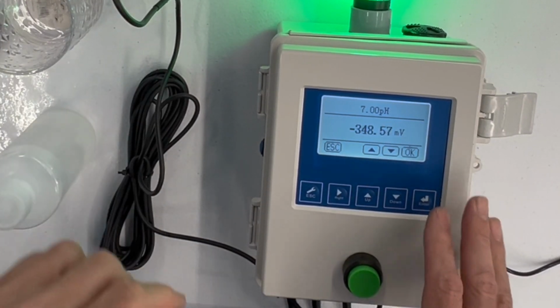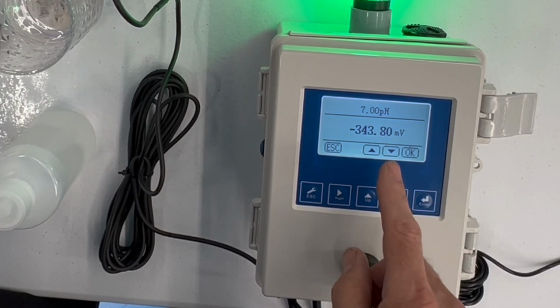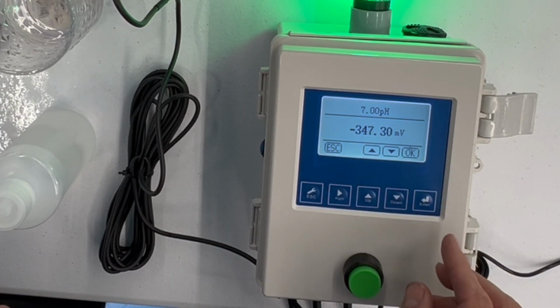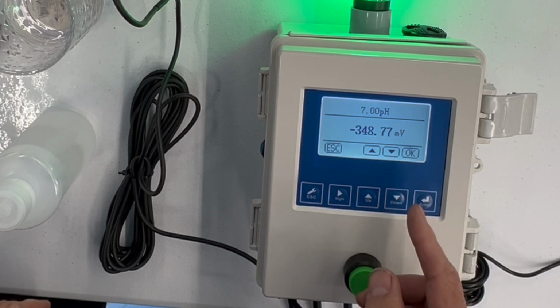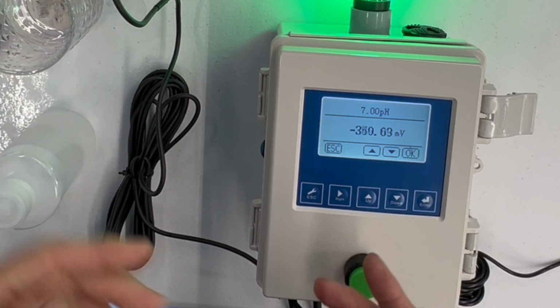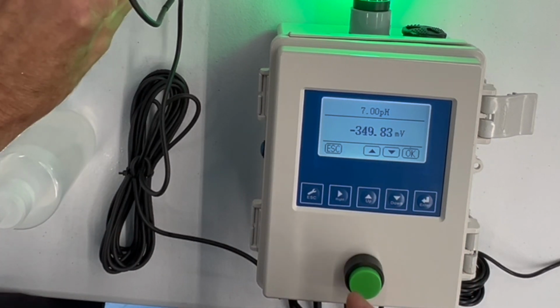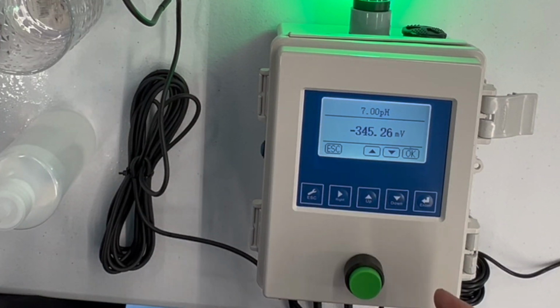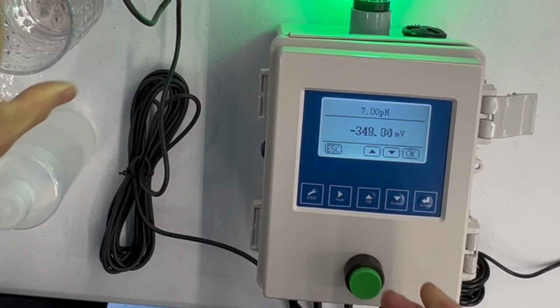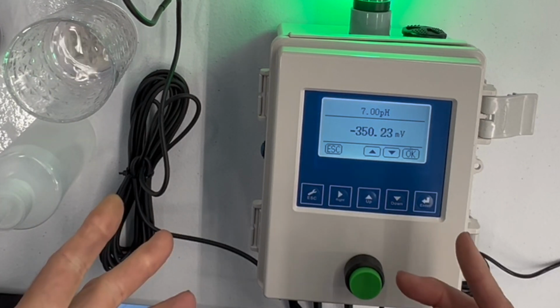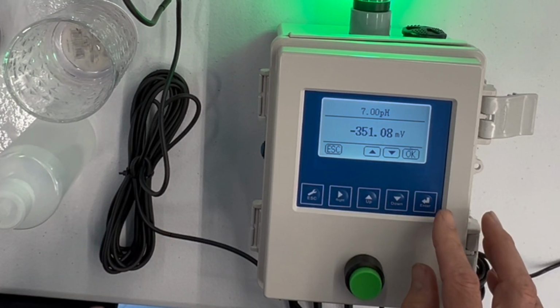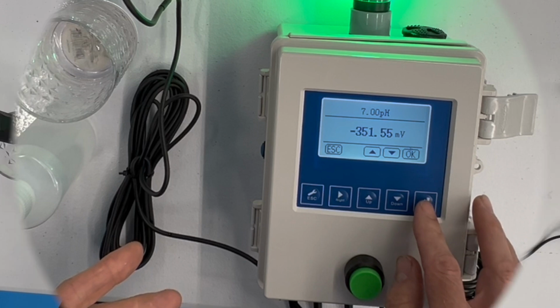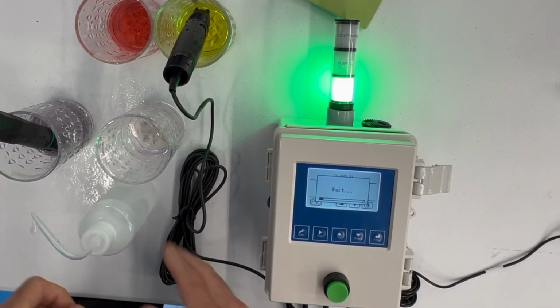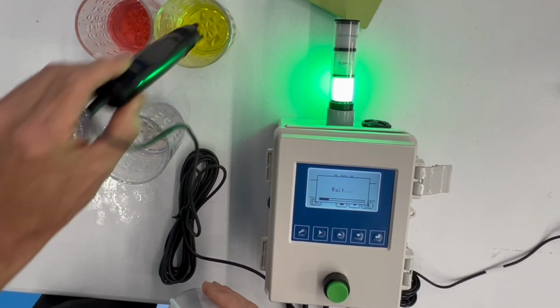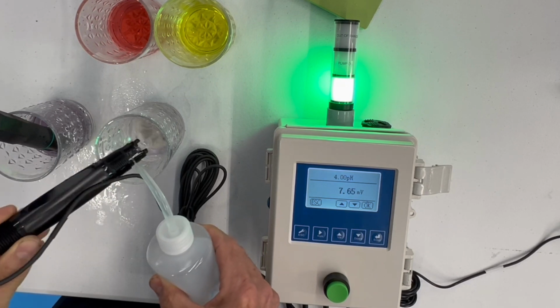Now the first thing you notice is that the millivolt reading is not 0 like you would expect from a standard pH probe. It's minus 350. That's okay, that's expected, and it's going to compensate through its algorithm inside. So that's pretty stable, around 350. It doesn't have to be exact, so we'll just say yes to that. And what we'll do is now put it in the 4 buffer.